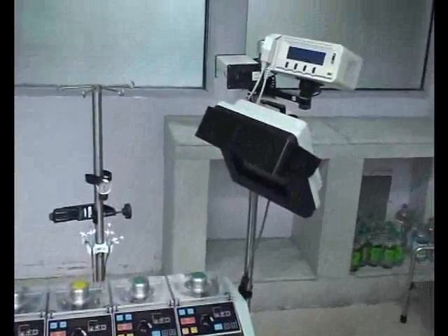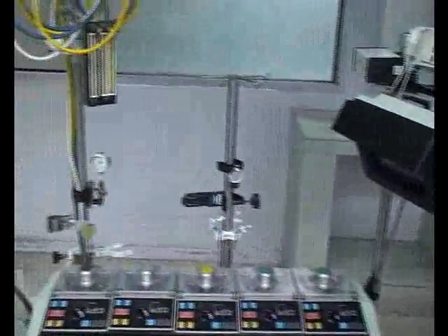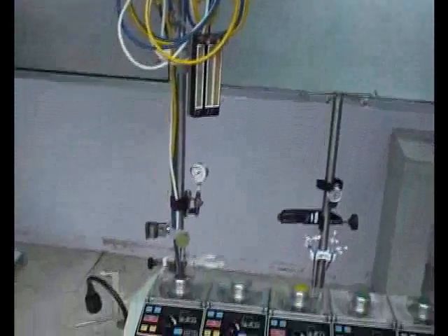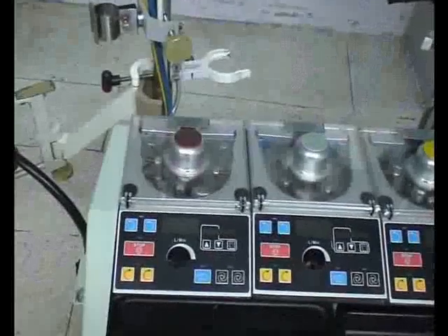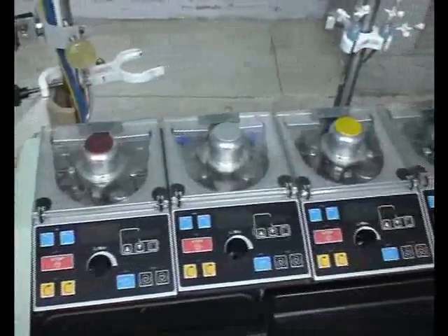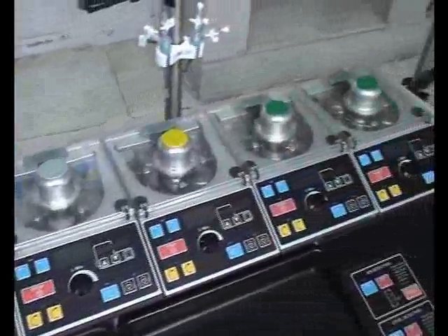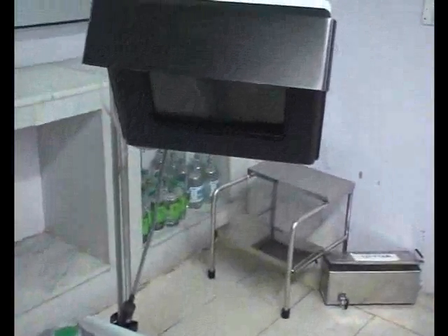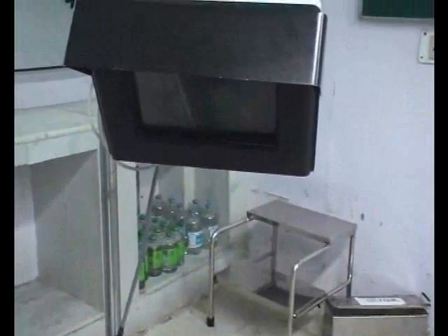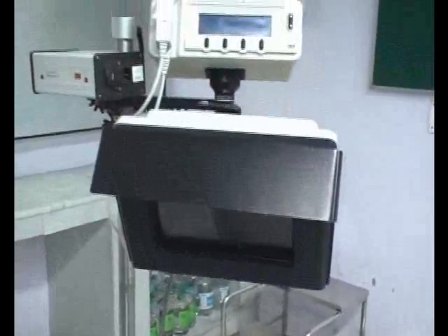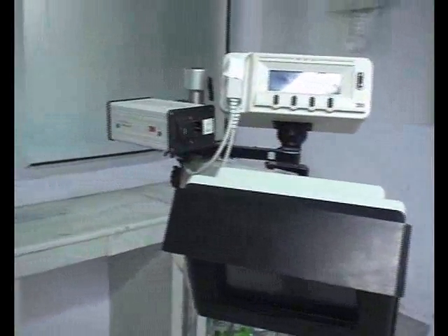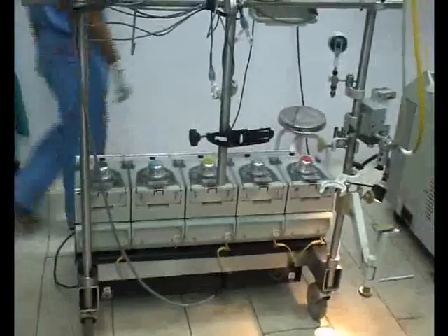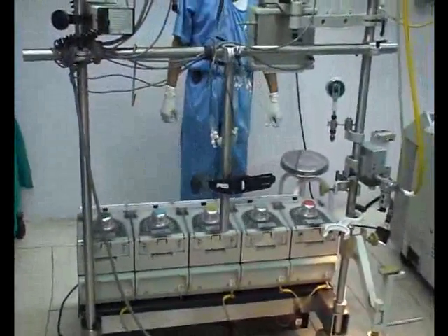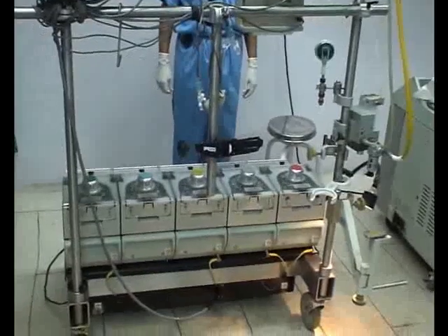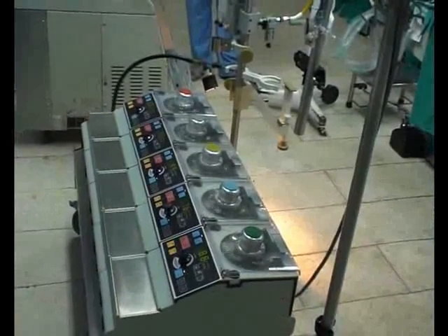The most expensive and technologically advanced is the pump. This modern 5-pump console is commonly used in most heart centers. The first, or the red pump, is the arterial pump. The other 4 pumps are used for cardioplegia delivery, cardiotomy suction, and intracardiac vent. They are color-coded.